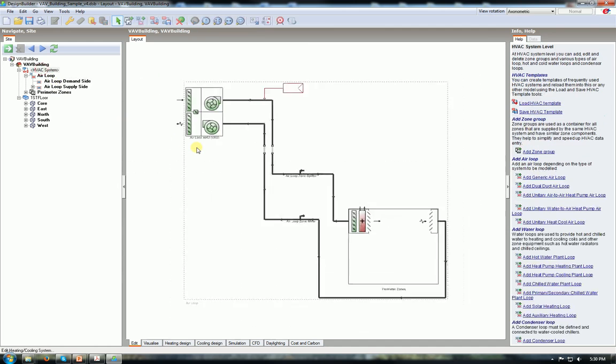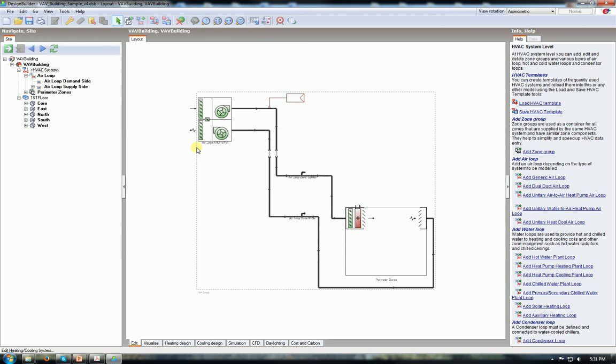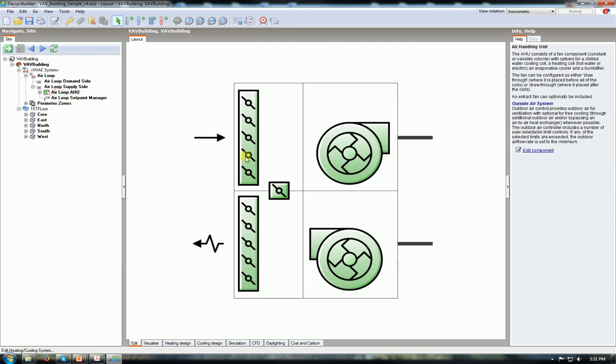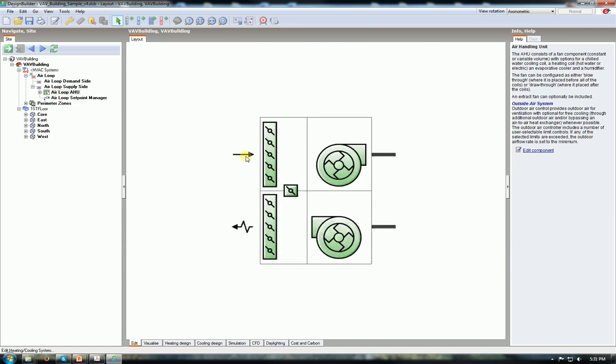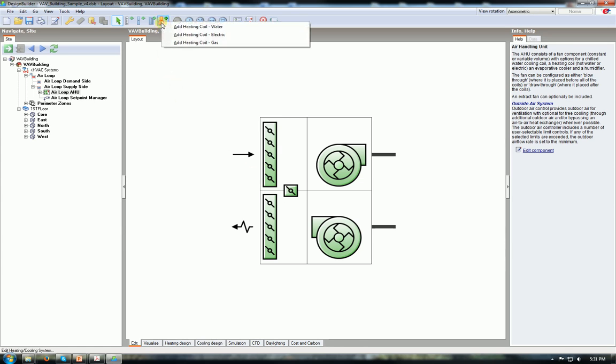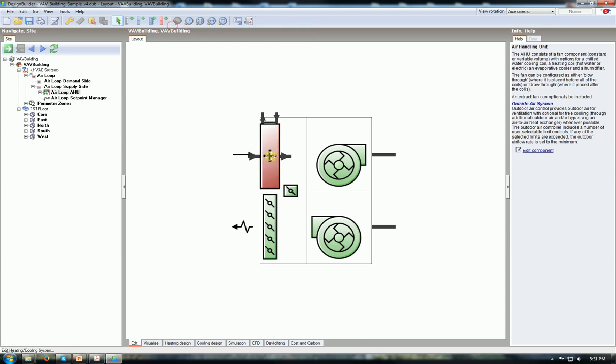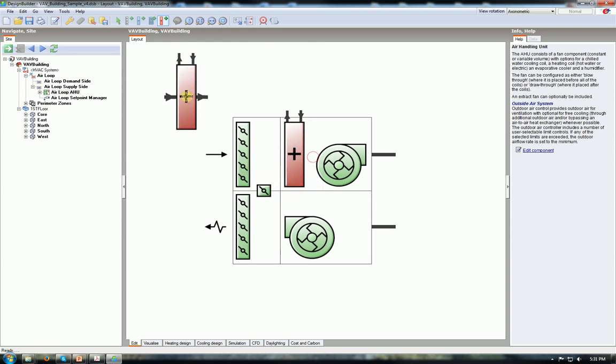Go to the HVAC system again. You see something is missing in this AHU. We have missing heating and cooling coil. We need to add this. Go to the air loop AHU. And then look at the top view. And we see add heating coil - not electric, not gas. It's hydronic system. So we should add heating coil water. And just add it before the fan and place it.